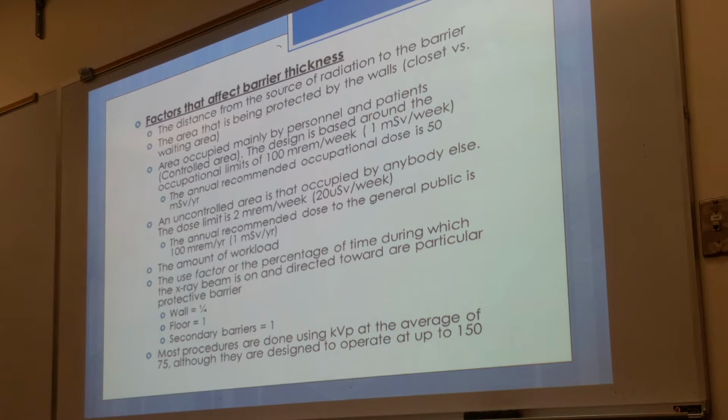The floor is going to be assigned a use factor of 1, and the secondary barriers will also be assigned the use factor of 1. That's an interesting number. The wall has a use factor of 1/4. Got it? You guys got it?